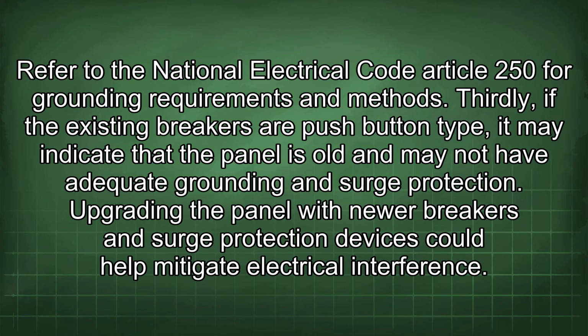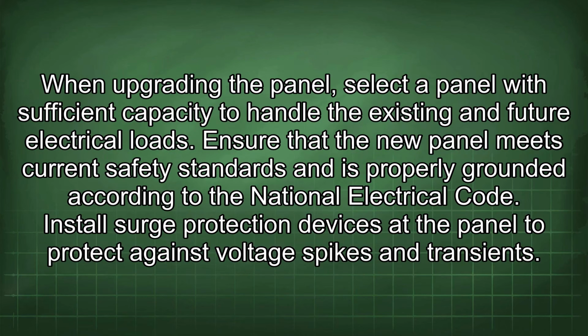Thirdly, if the existing breakers are push-button type, it may indicate that the panel is old and may not have adequate grounding and surge protection. Upgrading the panel with newer breakers and surge protection devices could help mitigate electrical interference. When upgrading the panel, select a panel with sufficient capacity to handle the existing and future electrical loads. Ensure that the new panel meets current safety standards and is properly grounded according to the National Electrical Code. Install surge protection devices at the panel to protect against voltage spikes and transients.